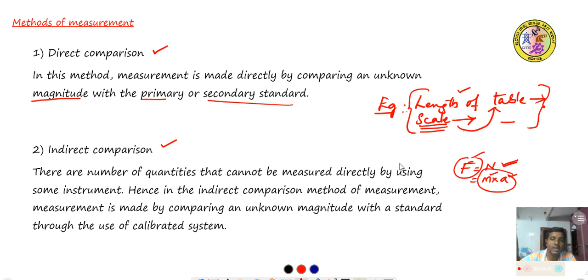The indirect comparison method of measurement is made by comparing an unknown magnitude with the standard through a calibrated system. Indirect comparison is very much used nowadays because compared to direct comparison, it is more accurate and human involvement is less, meaning errors are less compared to direct comparison.